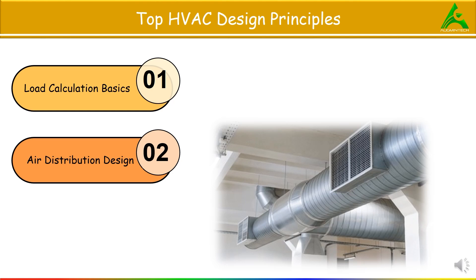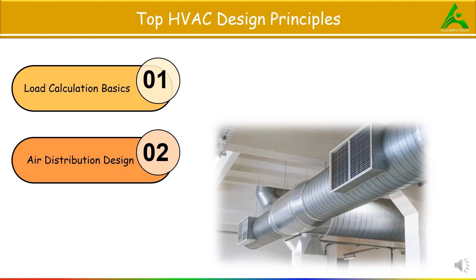For example, in a movie theater, ducts are designed using the equal friction method to achieve consistent airflow. Diffusers are placed above the seating rows directing cool air downwards, and a return air path near the floor prevents air stagnation. The result is a comfortable experience for viewers with no noticeable drafts or warm spots.